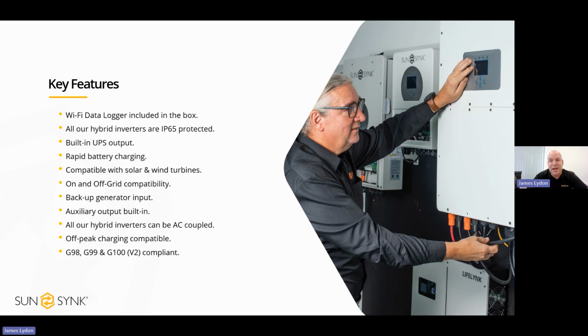As I've just mentioned, when that generator power comes into us, it goes two ways. If you've got a max potential load of 4 kilowatt, that 4 kilowatt load is going to take most of the generator power. So with 150% oversizing, an 8 or a 10 kVA generator, that leaves enough headroom to power that maximum load, but also charge the batteries at the same time.